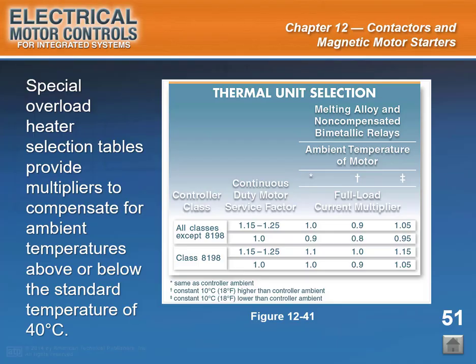Most heater manufacturers provide special overload heater selection tables that provide multipliers to compensate for temperature changes above or below the standard temperature of 40 degrees Celsius. The multipliers ensure that the increase or decrease in temperature does not affect the proper protection provided by the overload relay. End of slide 51.